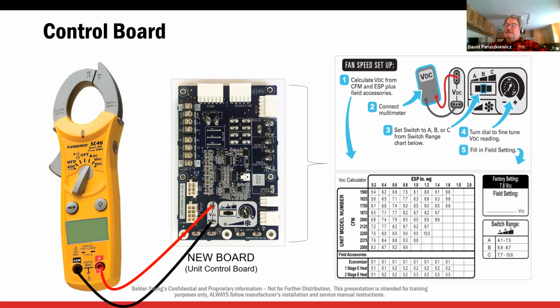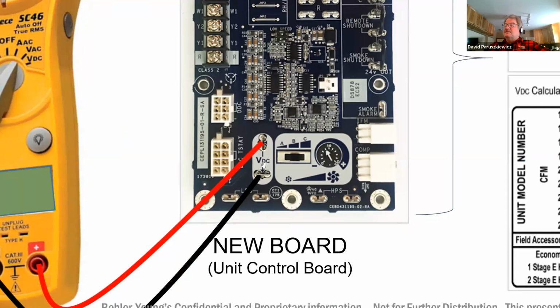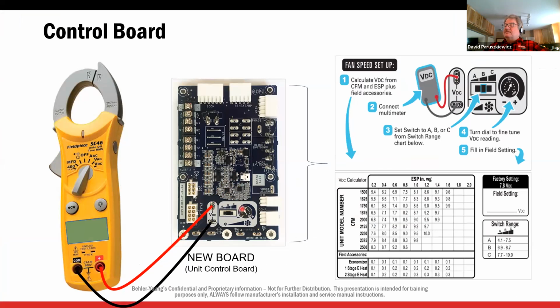So I take my DC voltmeter here, and on the central terminal board, you'll see that it says VDC. They look like female spade connectors. You put your red probe in the top positive, the black probe in the bottom negative. And then we're going to adjust the switch first, and then this dial till we get 9 volts DC. So the switch is for a range. Position A is 4 to 7.5 volts, B is 6.9 to 8.7, C is 7.7 to 10 volts DC. So we need 9, so that would fall in C.